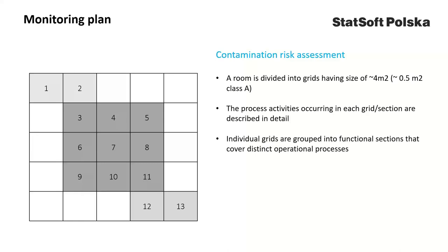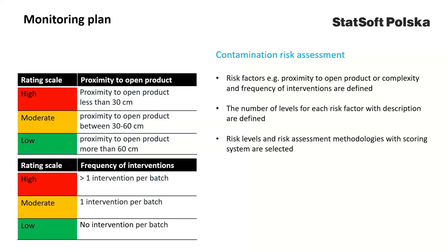Individual grids can be grouped into functional sections that cover distinct operational processes, such as in-feed, filling, or closing. In the next step, we determine the contamination risk factors, such as distance from the open product, or complexity and frequency of interventions. For each factor, the number of levels is defined with a description, and the method of risk estimation is selected, which can be additive by summing the risk factors, multiplicative by multiplying the factors, or a method of risk sorting and filtering. Then a scoring system should be defined to differentiate between high, moderate, and low risk of contamination.